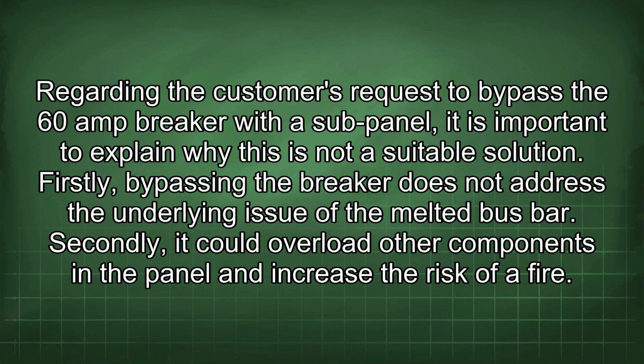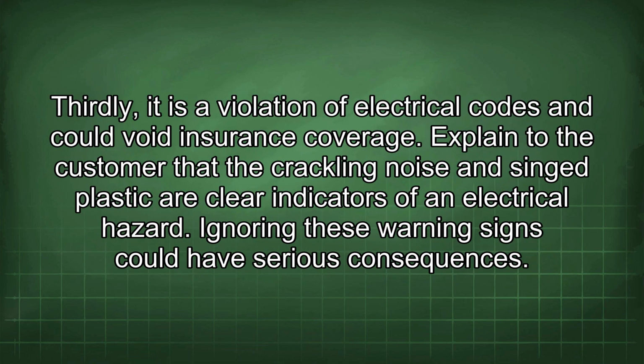Regarding the customer's request to bypass the 60-amp breaker with a sub-panel, it is important to explain why this is not a suitable solution. Firstly, bypassing the breaker does not address the underlying issue of the melted bus bar. Secondly, it could overload other components in the panel and increase the risk of a fire. Thirdly, it is a violation of electrical codes and could void insurance coverage.